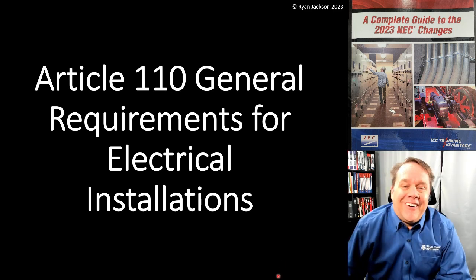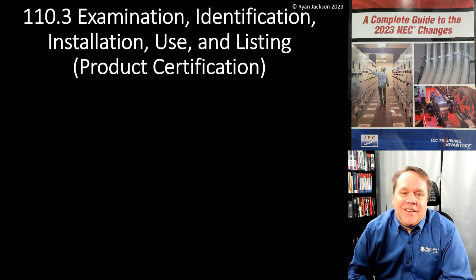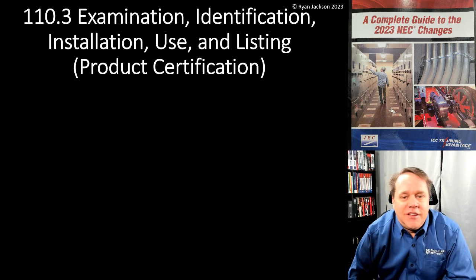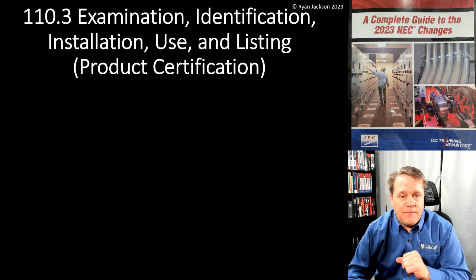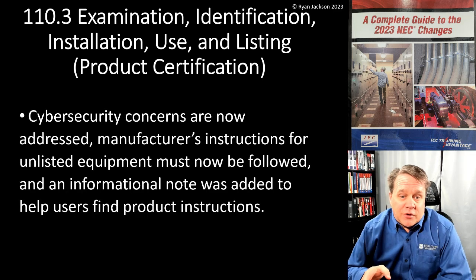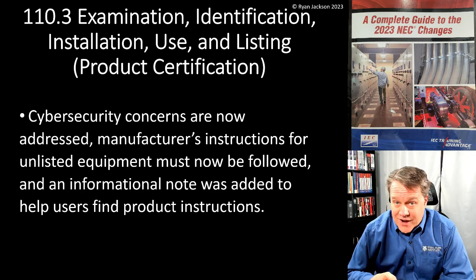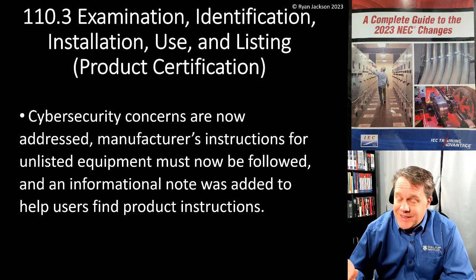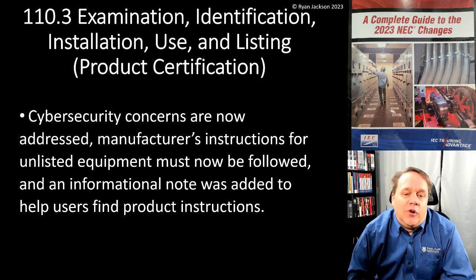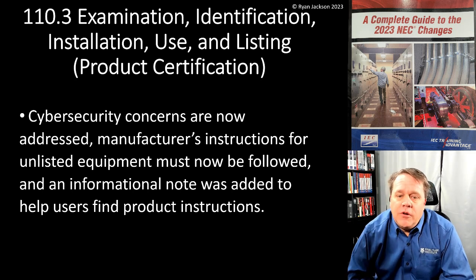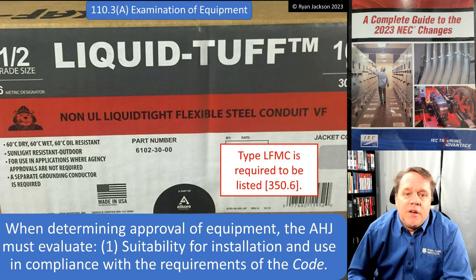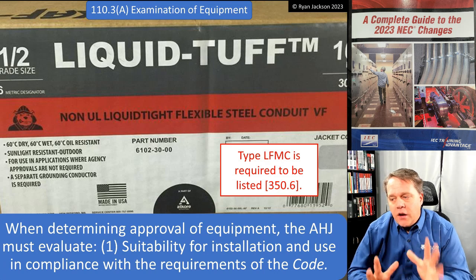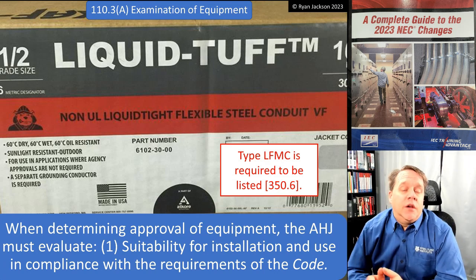First thing is examination, identification, installation, use, and listing — also known as product certification — in Section 110.3. Cybersecurity concerns are now addressed; never thought we'd be talking about that in the NEC. Manufacturers' instructions for unlisted equipment must now be followed, and an informational note was added to help users find product instructions. A lot of people jump into 110.3(B) because that's the rule that says you have to use listed products in accordance with the listing instructions.